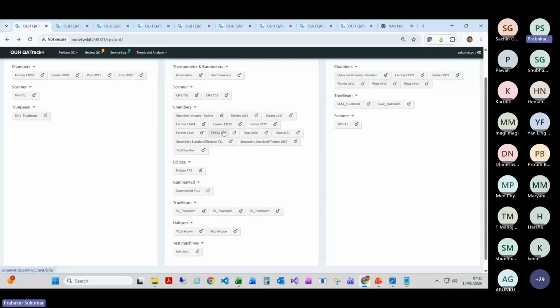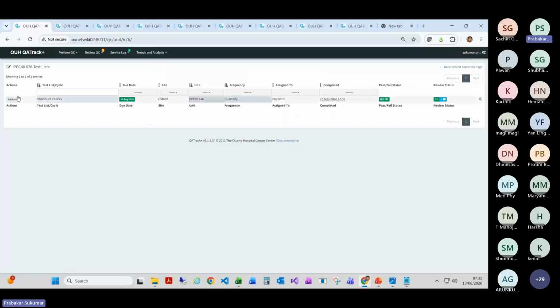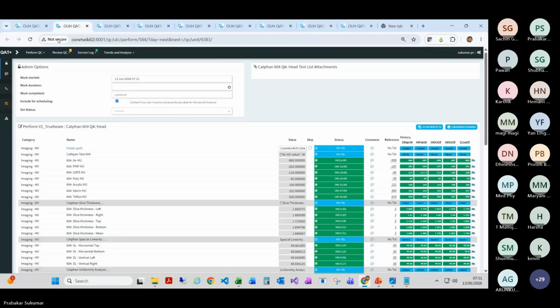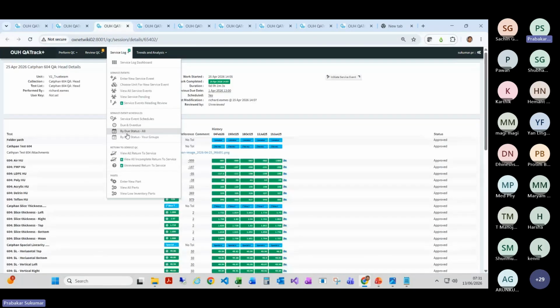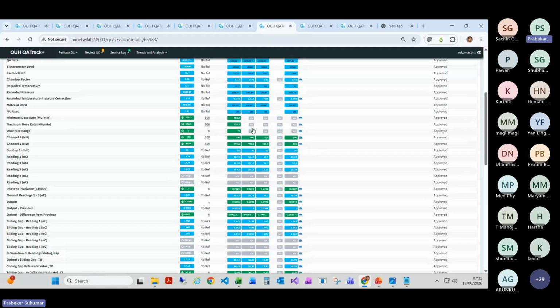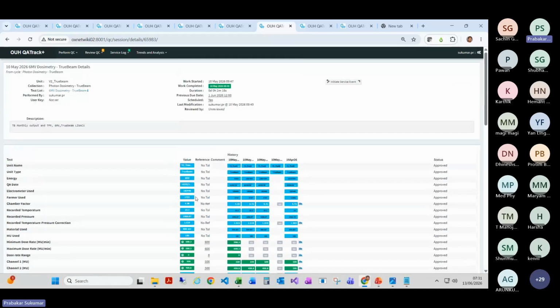I'm checking whether we are doing strontium checks, and we use it in the output, which chamber has been used in performing the output measurements. One second. There are some outputs. You can see here which chamber they have utilized. We want to check whether the leakage and strontium checks have been performed, when they were performed, whether it has been calibrated, whether it has cross-calibrated numbers, so that it is quite easy to track which chamber they used for which machines.